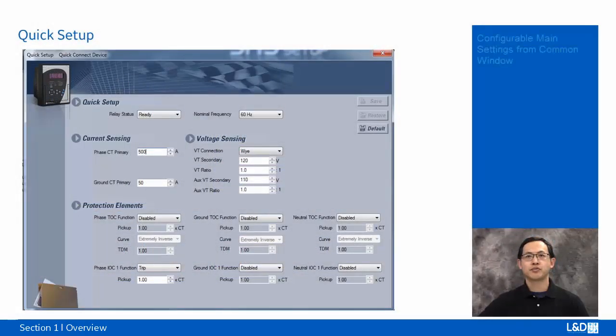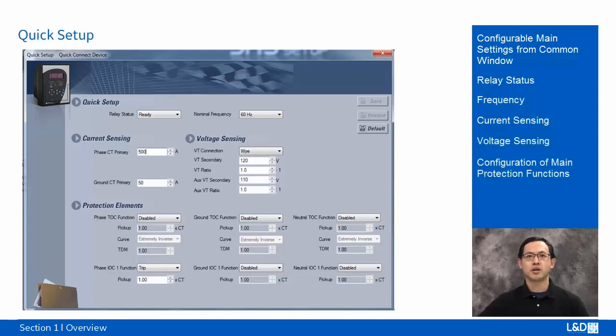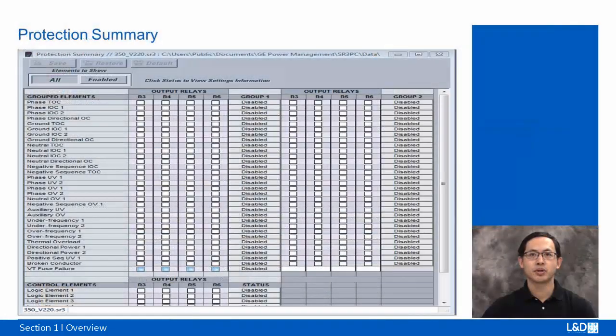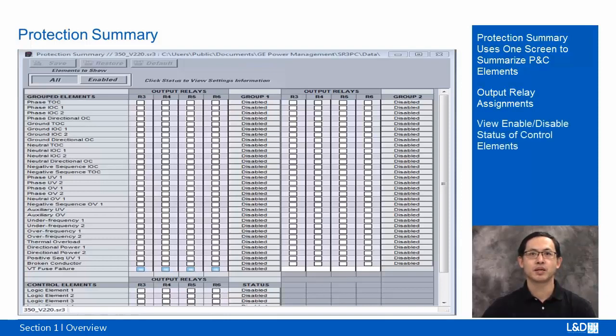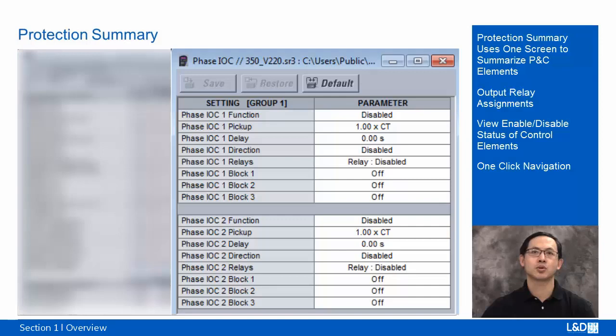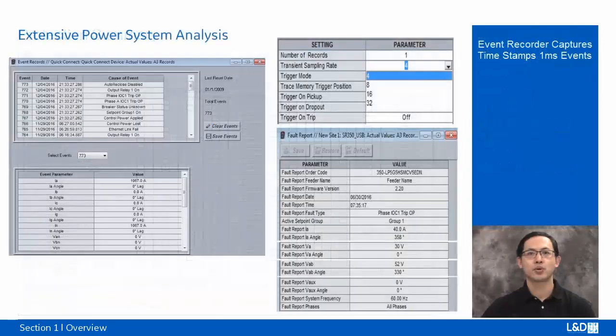Quick setup allows the user to configure main settings from different screens in a common window: relay status, nominal frequency, current sensing, voltage sensing, configuration of main protection like phase, ground, neutral, time overcurrent, and instantaneous overcurrent. Protection summary uses one single screen to show summarized information of settings for protection and control elements, and output relay assignments for the elements. User can view the enable, disable status of control elements, as well as navigate to the respective protection element screen on one button click.